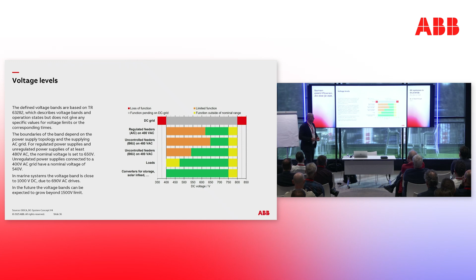So how do we implement the voltage control? Essentially, the idea comes from AC systems. Unsurprisingly, many ideas here are reused and recycled, just adjusted, and it's the droop. In AC systems, we use droop for frequency control. In DC, we use the droop method for controlling the voltage. Essentially, we design a curve for each source converter able to source current in the system, and we link the current and the voltage with the resistance.